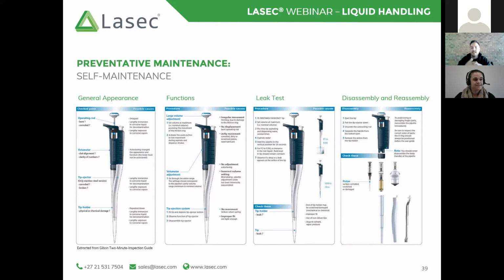So if you do dismantle it just to clean it out or perform preventative maintenance, you shouldn't need to worry about the calibration all too much, provided that you do it with care and you are gentle in the dismantling of your pipette. If you do decide to change parts, such as your piston assembly or your tip holder, you are going to be required to recalibrate that pipette.